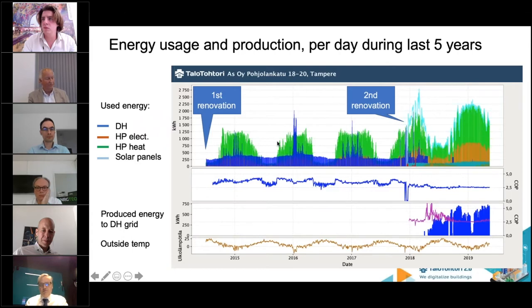And here we can see the energy usage over the 5 years. The first renovation part, where all these graphs begin, was the phase when the exhaust air heat recovery units were installed. The blue curves are the district heating energy consumption. The green one is the energy produced locally by the heat pumps. This is a 1 year cycle, then it's summertime and the next year cycle, and so forth. In the middle part of the graph you can see the blue line. This is the COP of the heat pumps, the system level COP. It's not very clear here, but it varies from 3 to 4, typical for this kind of exhaust air heat recovery systems.